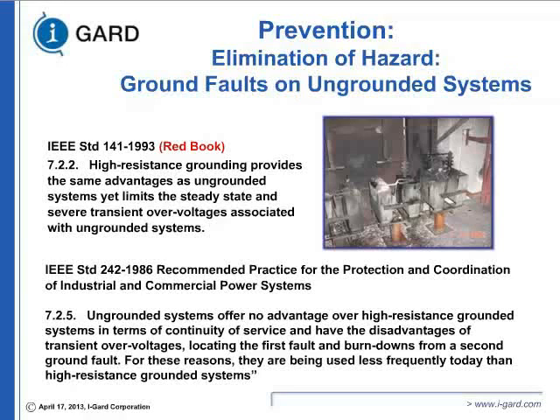Some other documents that you might be familiar with. IEEE Standard 141, which is the Red Book, tells you that high resistance grounding provides the same protection as an ungrounded system. Why did industry used to use ungrounded, delta systems? Mainly not to go down on the first fault. It creates environmental issues, it might concern safety issues. So the Red Book tells you that it gives you all the advantages that you had, plus you can have some detection.